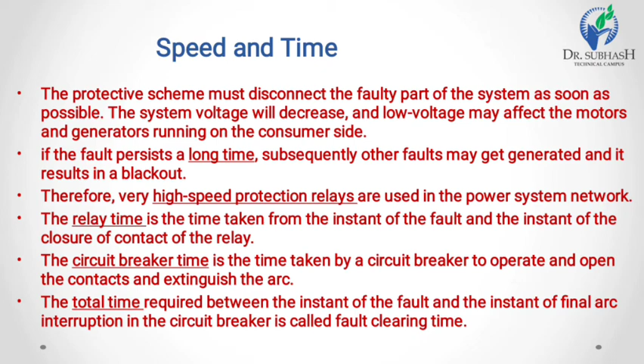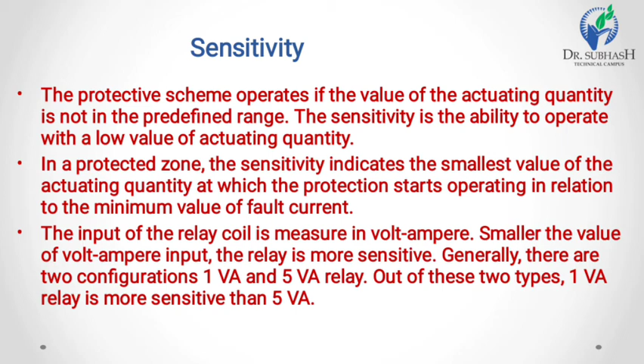Now, what is sensitivity? A protection relay should operate when the magnitude of the current exceeds the preset value. This value is called the pickup current. The relay should not operate when the current is below its pickup value. A relay should be sufficiently sensitive to operate when the operating current just exceeds its pickup value. The input of the relay coil is measured in VA, volt ampere. The smaller the value of volt ampere input, the more sensitive the relay is. Generally, there are two configurations, 1 VA and 5 VA. Out of these two, the 1 VA relay is more sensitive than 5 VA.